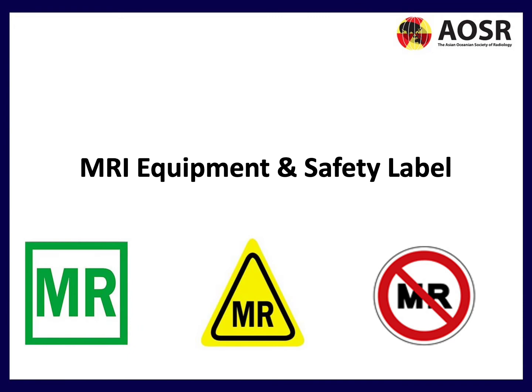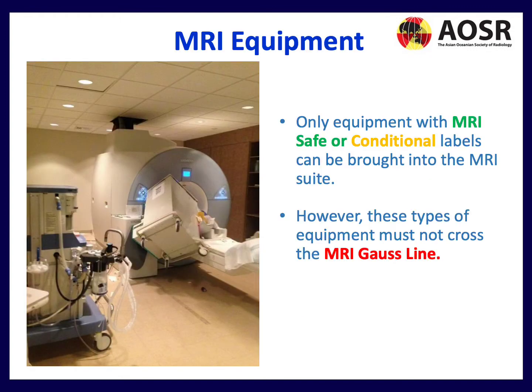So let's move on and cover MRI equipment and safety labels. We're going to talk about the different labels shown below. For MRI equipment, only equipment with the MRI safe or conditional labels can be brought into the MRI suite. However, even if the equipment is potentially safe, it must not cross the MRI Gauss line, otherwise you're going to get a situation as we see here in this picture, where that has been dragged in, and that poses a massive risk to both patients and staff members.